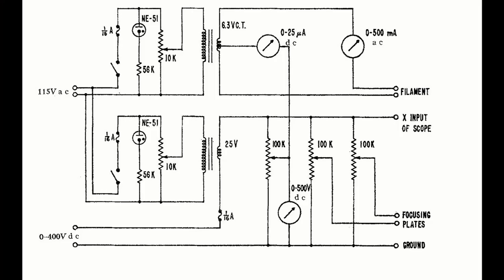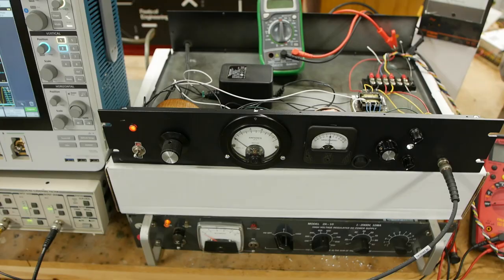That would be equivalent to applying a changing magnetic field to move this path of ions back and forth. We sweep through different magnetic field strengths. Stronger magnetic fields curve the particle beam more tightly than weaker fields. This is a totally valid way to do it. But the problem is we need a huge electromagnet and we need to control it very carefully. We might have problems with hysteresis. So there's another trick. Instead of changing the magnetic field strength, which would be equivalent to rotating the prism, we're going to change the incoming ion beam speed. We're going to change the acceleration voltage back and forth.